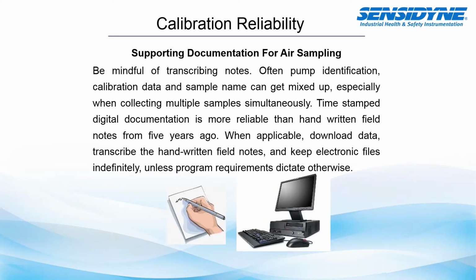Be mindful of transcribing notes when performing your air sampling calibration. Often pump identification, calibration data, and sample name can get mixed up, especially when collecting multiple samples simultaneously. Time-stamped digital documentation is much more reliable than handwritten field notes from 5 years ago. When applicable, download data, transcribe the handwritten field notes, and keep electronic files indefinitely unless your particular program requires or dictates otherwise.